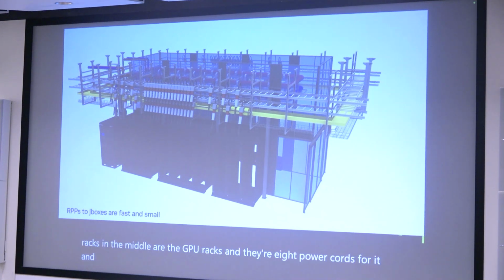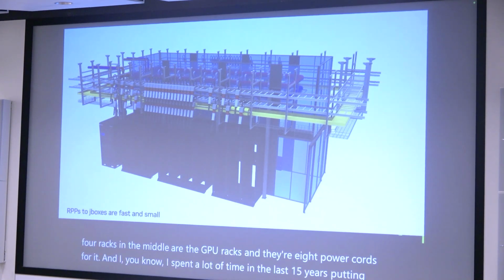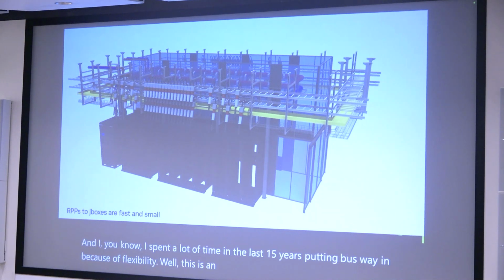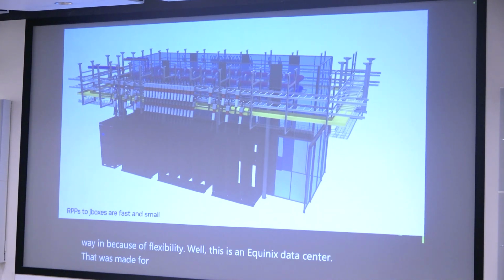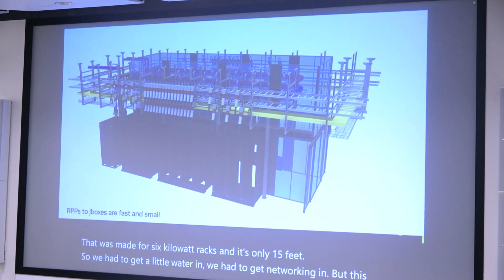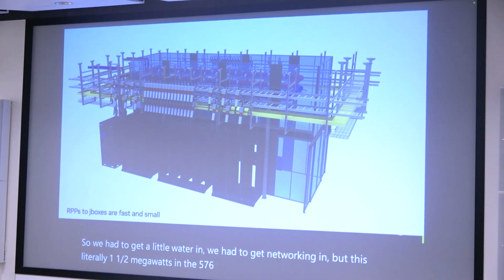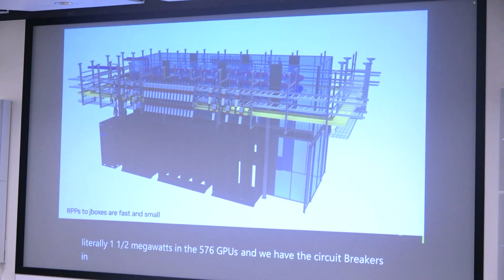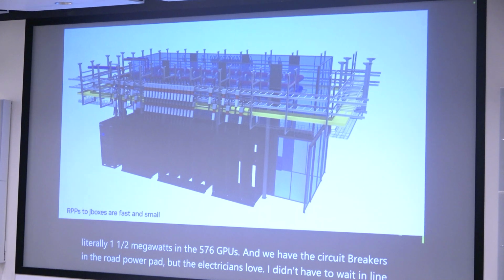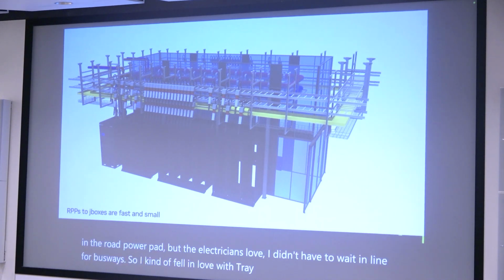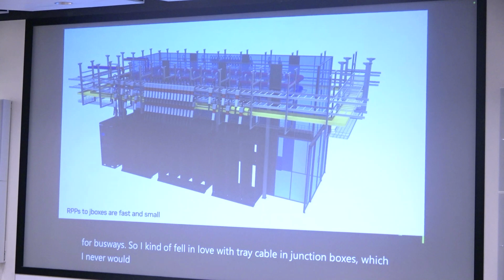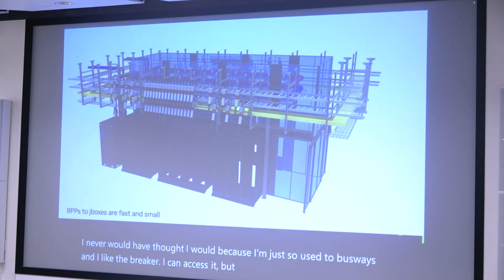And I spent a lot of time in the last 15 years putting busway in because of flexibility. Well, this is an Equinix data center that was made for 6 kilowatt racks, and it's only 15 feet. So we had to get water in, and we had to get networking in. But this is literally 1.5 megawatts in these 576 GPUs, and we have the circuit breakers and the row power panel. But the electricians loved it. I didn't have to wait in line for busway. So I kind of fell in love with tray cable and junction boxes, which I never would have thought I would, because I'm just so used to busways, and I like the breaker. I can access it.